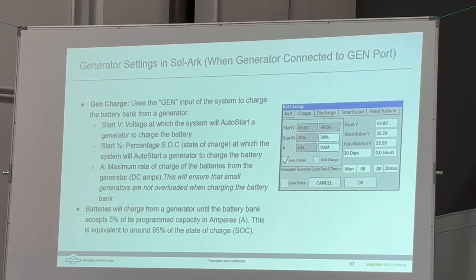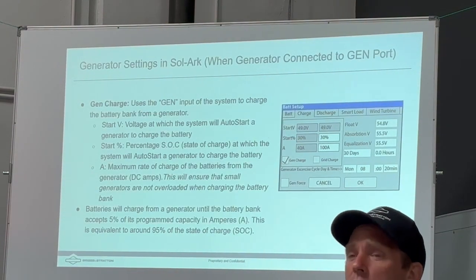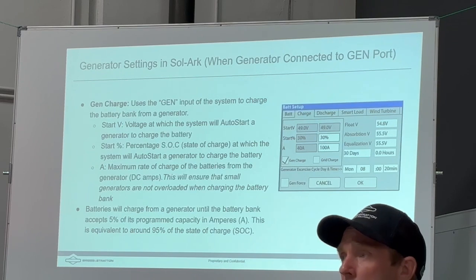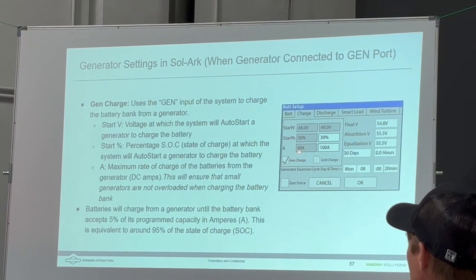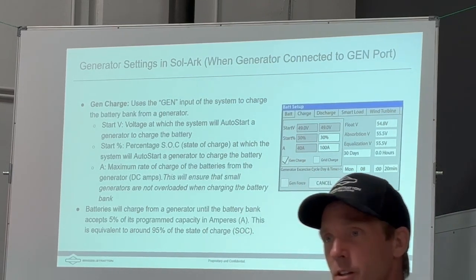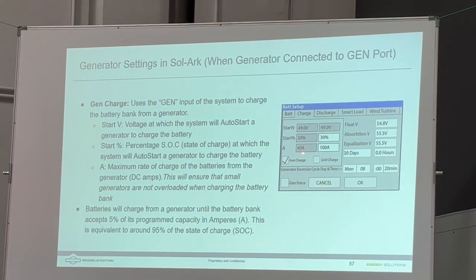The other thing that you have the ability to do, and we're going to get into this a little bit on the charge, the ways to set up charge. So this column corresponds to generator charging, and this column on settings corresponds to grid charging. You can limit how much power you want to pull off the generator. So if I want to charge my batteries off of a generator, but I've only got maybe a 13K generator, and I think the house might consume, say, 5K, I can limit how much current I'm going to pull for the battery charging. Keep in mind, this is DC current, so 40 amps times 50 volts, that's only 2,000 watts, right? A lot of installers, especially generator installers, think that this is 40 amps at 240 volts, right? So that would be like 9 kilowatts.